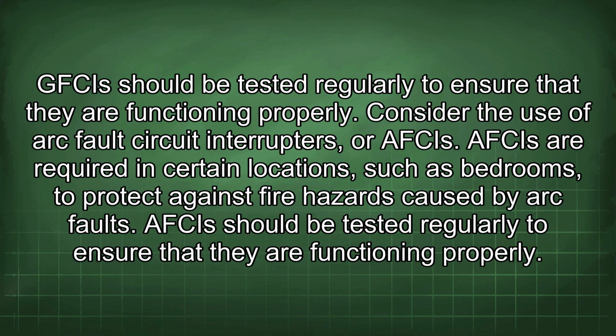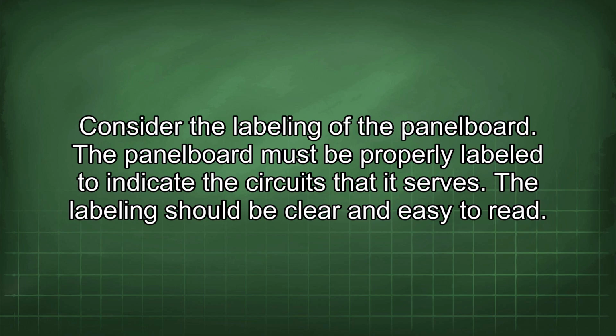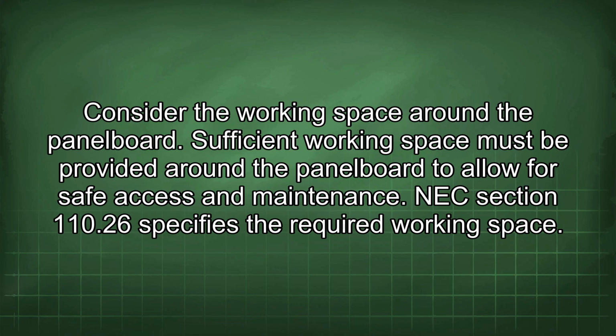Consider the use of arc fault circuit interrupters, or AFCIs. AFCIs are required in certain locations, such as bedrooms, to protect against fire hazards caused by arc faults. AFCIs should be tested regularly to ensure that they are functioning properly. Consider the labeling of the panel board. The panel board must be properly labeled to indicate the circuits that it serves. The labeling should be clear and easy to read. Consider the working space around the panel board. Sufficient working space must be provided around the panel board to allow for safe access and maintenance. NEC Section 110.26 specifies the required working space.